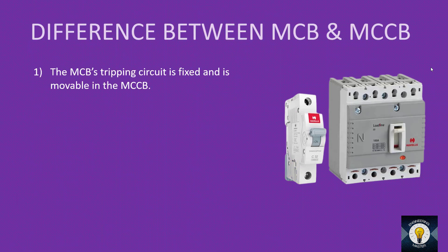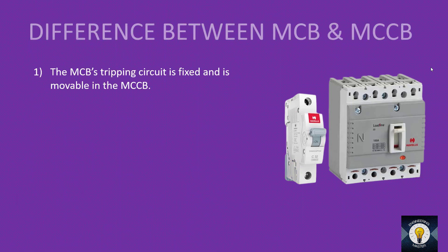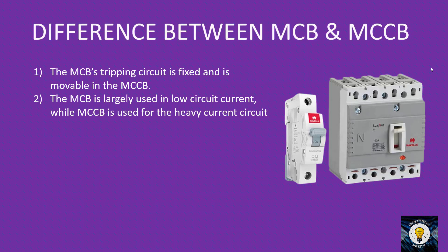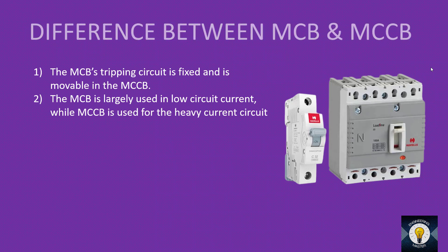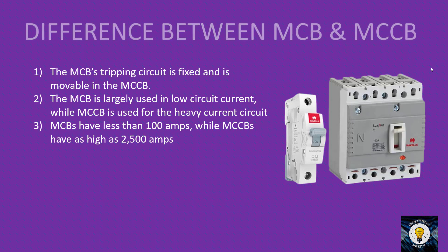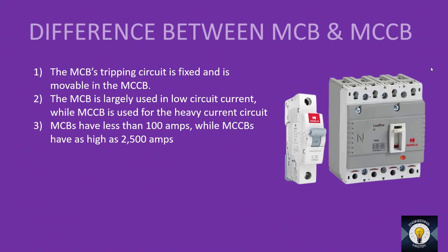What is the difference between MCB and MCCB? First, in MCB the tripping circuit is fixed, while in MCCB the tripping circuit is adjustable — this allows settings to be changed. Second, MCB is used for low-current circuits while MCCB is used for heavy-current circuits. Third, MCB has a rating of less than 100 A while MCCB is available from 16 A to 2500 A.